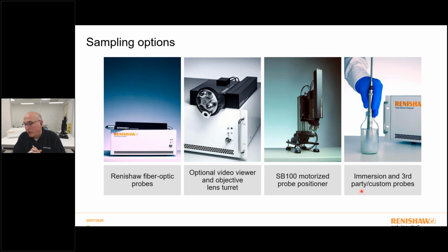Now, in terms of how you might want to sample, we have obviously the Renishaw fiber optic probes. We have an option for having a video module with those probes and maybe an objective turret. And then you also have the option of being able to motorize the position of that whole assembly using this SB100. So I'm going to get into these quite a lot, and then I'm going to come back into the immersion and third-party probes a little bit later. But once you actually have this kind of capability, the motorized microscope objective turret, you now have a Raman imaging microscope system. So this is now a portable system with fiber probes that can still retain all the great capability of a standard optical Raman microscope system.